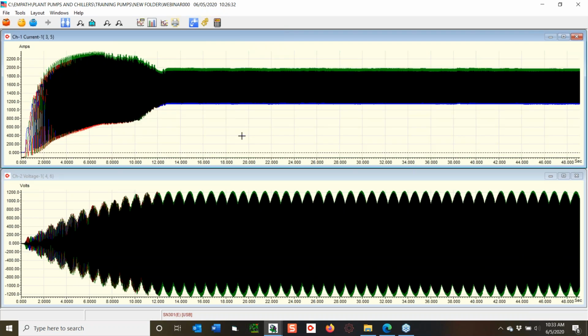So what we're going to do is look at the current envelope, and that's what the curve just happened to look like because it's on a VFD. If I started in inrush, it would peak and then come right back down to where it's supposed to.